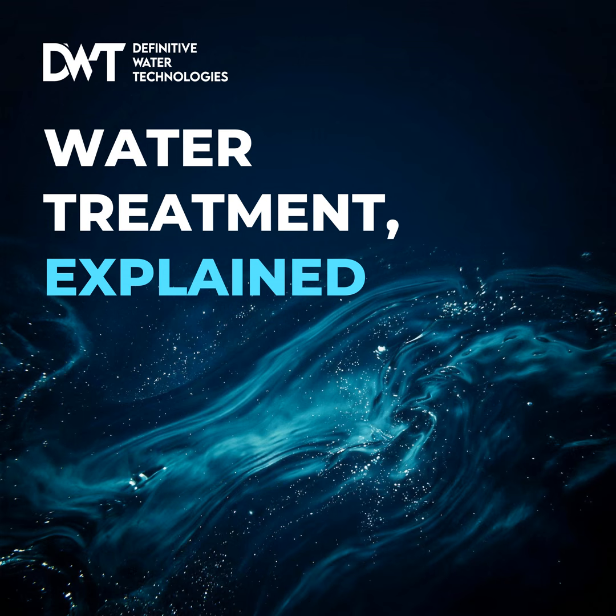hypochlorite gassing problem. Okay, what happens with hypochlorite? So sodium hypochlorite, standard industrial bleach, is notoriously unstable. As it sits in the day tank, especially as it gets warm in a South African plant room, Oh yeah, midsummer. Right, it naturally degrades and releases oxygen gas bubbles. Okay. Now, imagine your standard diaphragm pump. It relies on a basic hydraulic rule. Yeah. Liquid is incompressible. The diaphragm pushes, the liquid has nowhere to go, so it lifts the check valve ball and squirts out. Right, it forces the mechanical gate open.